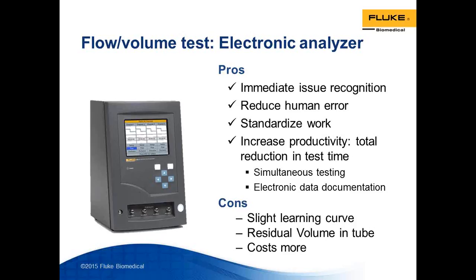Of course, there are some strong pros associated with this. You have immediate issue recognition because you can see the results right on a graph, if your infusion pump tester allows you to do that. And here we have featured one of our infusion pump analyzers, the ID5, where you can see on a graphical display exactly what the pump characteristics are. So if you're an organization that needs a lot of comprehensive test data, trending and analysis, this is a very powerful tool to have at your disposal.